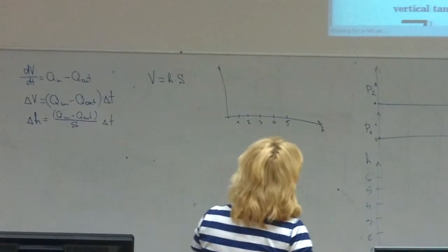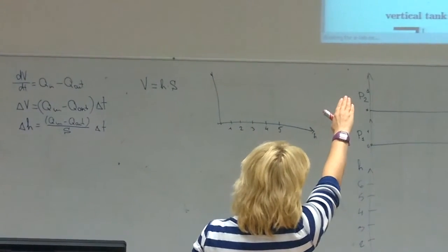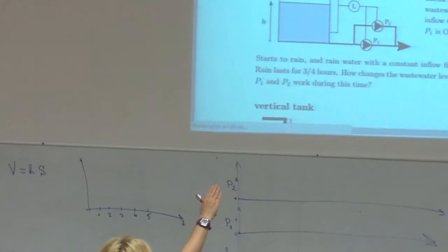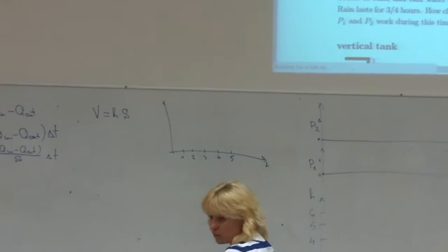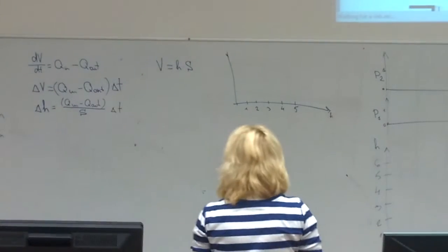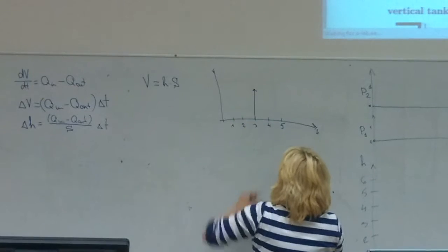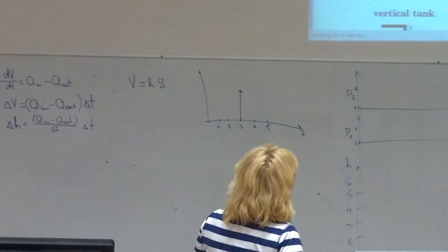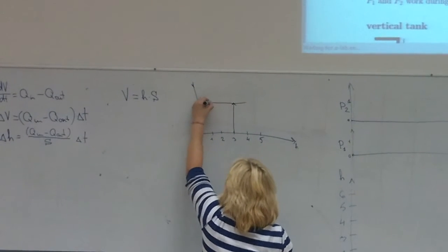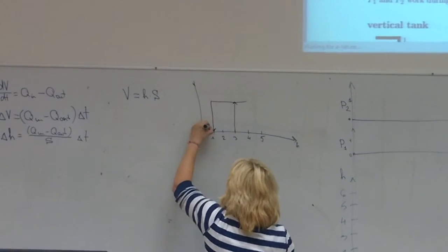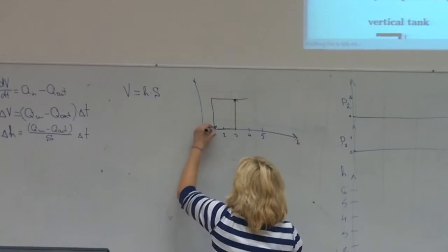And I have been told that the first pump is placed in service when the height is equal to 3. So basically that means that the first pump is turned on at this height and turned off when the height is equal to 1. So as you can see, here we have such a hysteresis.